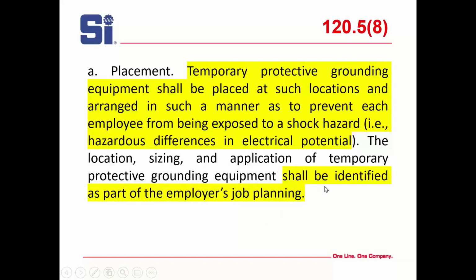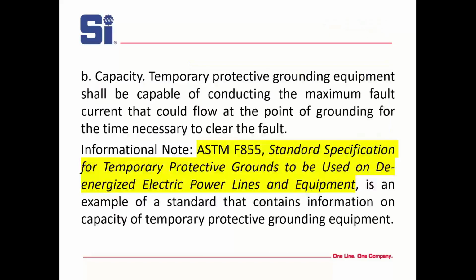And the application of temporary protective grounding equipment shall be identified as part of the employer's job planning. A lot of people don't plan very well. Let me tell you, grounding is so important. Of course, again, just like OSHA, it has to be able to carry the maximum fault current. And for those of you who are not familiar with ASTM F855, it looks like a lot of people were, that's good. This is where all your grounding specifications are located.